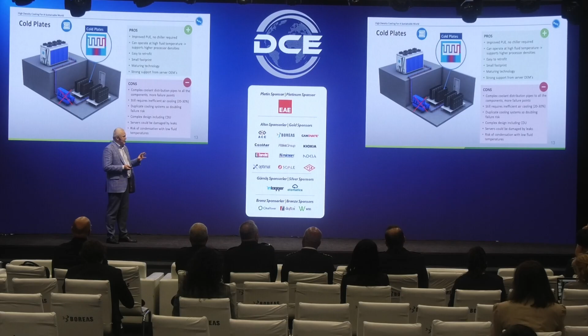You have a fluid cooler on the roof, which could be dry, as one of yesterday's speakers mentioned. But if you want to avoid the peak, you can install pads in this dry cooler and wet them, so the air passes through these wet pads before hitting the coil, to increase efficiency. So basically the unit is now driven by wet bulb temperature versus dry bulb temperature. Those are some technicalities.